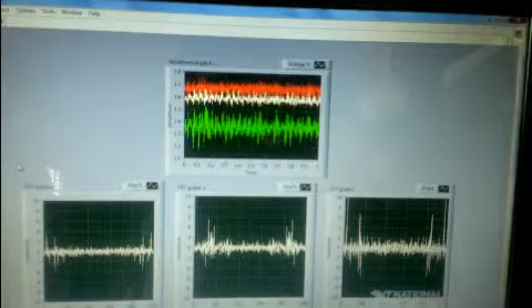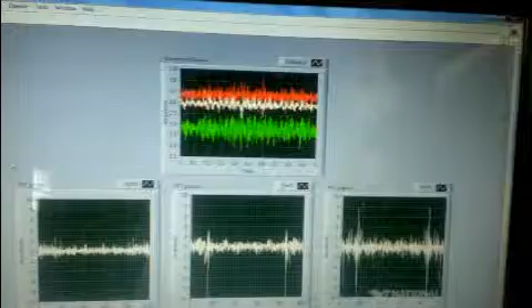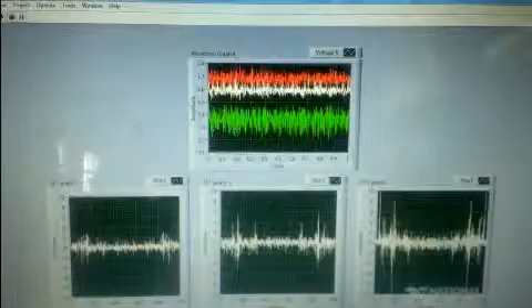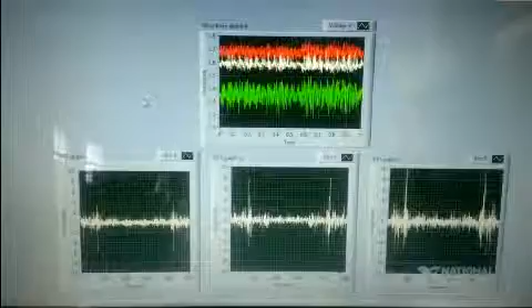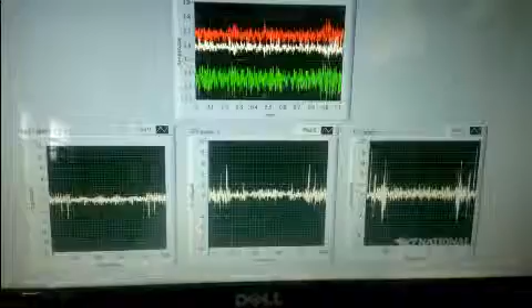So initially we are taking some data without running the motor, and then we are taking some data after running the motor. We subtract both sets of data so that we get only the data pertaining to the signature analysis of the shaft. Having taken the data from the FFT, we can analyze what the problem with the motor is pertaining to the shaft. Having analyzed the fast Fourier transform, we can also generalize this for various other distributions, and we can derive the signature analysis for various other faults in the motor.